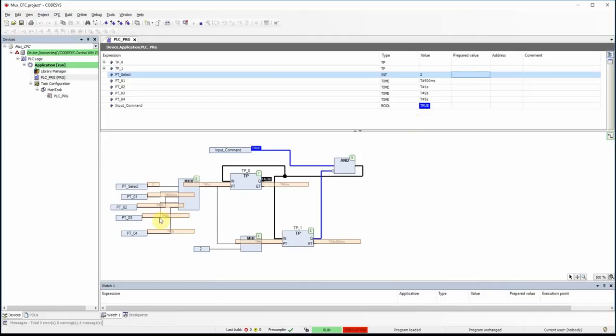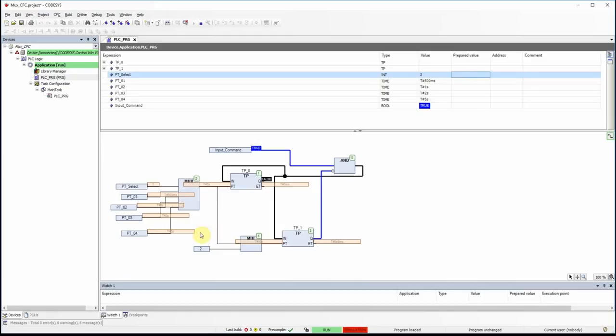I try with a value of 2 — F7 and Alt+F7 — and now we have 2 seconds on the first timer and 4 seconds on the second, so the pulse is 2 seconds on, 2 seconds off. With a value of 3 we have 5 seconds. If I provide a value bigger than 3 — say 10 — the multiplexer provides the last input as its output. Going back to 0, 500 milliseconds appears again.